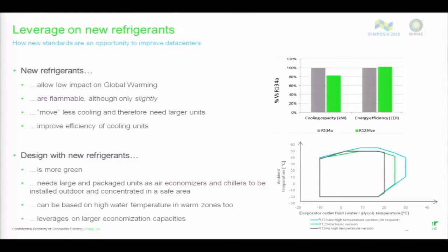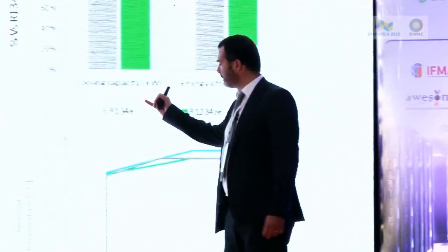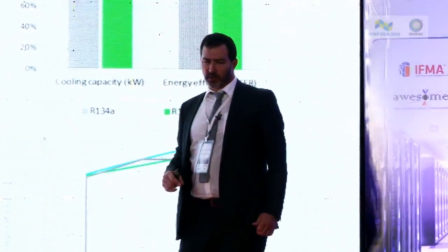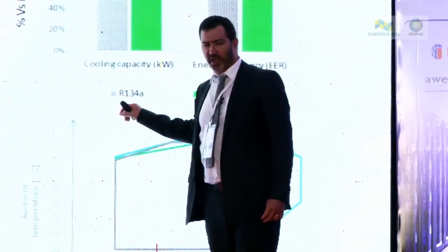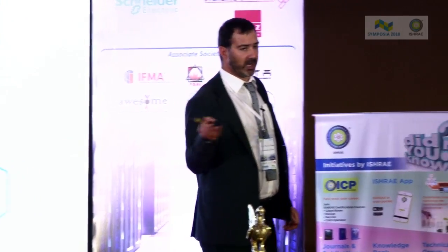There is a new blend in the middle that replicates the 134A and has a GWP of 700. However, the target for the Kigali agreement, and for all the other agreements, is to move to a refrigerant which has a GWP lower than 10.